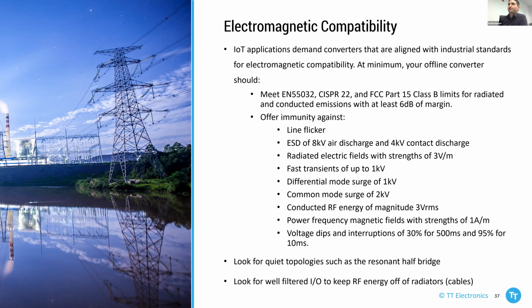Radiated fields of 3 volts per meter, fast transients (EFT) at 1 kV. We want differential mode surge protection of 1 kilovolt and common mode surge protection of 2 kV. Conducted RF energy immunity needs to be at least 3 volts RMS. Power frequency magnetic field is a fairly easy one at 1 amp per meter, and dips and interruptions are specified as well.